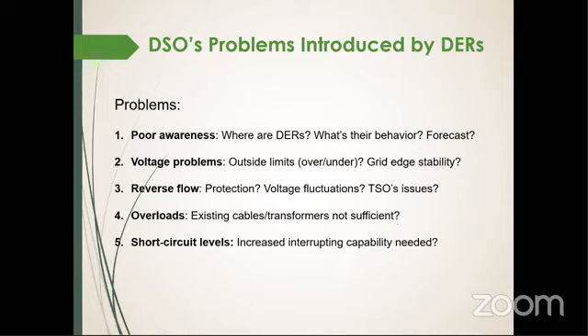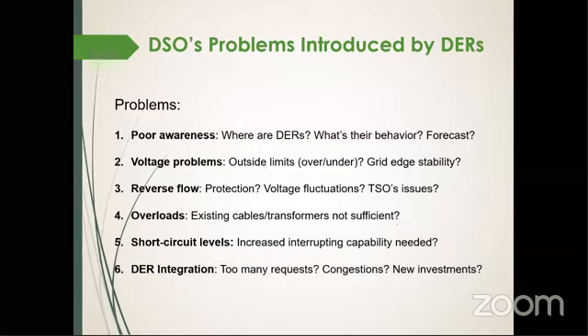Then short circuit levels. Now, short circuit current is not in a top-down direction anymore. We have short circuit currents flowing all over the place because of DERs, and more importantly, they are not predictable. They are changing in real time, so our protection equipment needs to be adapted in real time. We can't rely on traditional set-and-forget methods anymore.